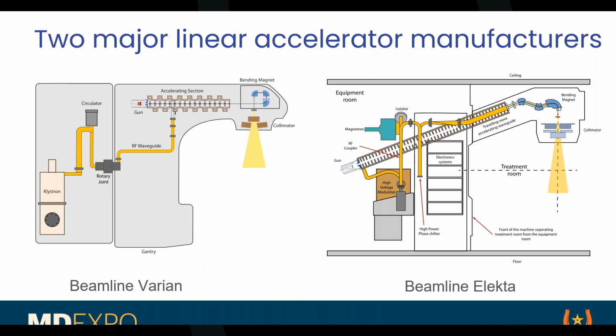The high voltage pulse uses some sort of pulse transformer tank. It's high voltage, it causes problems, and things get big. As I showed before, these machines have to rotate around the patient, so there's a rotary joint in between. On the Varian machine, there's a stand at the back and a rotary joint in the middle. The machine rotates around that joint, and then we have the beam delivery system, which I showed before: the accelerator, the bending magnet, and the dose collimation.